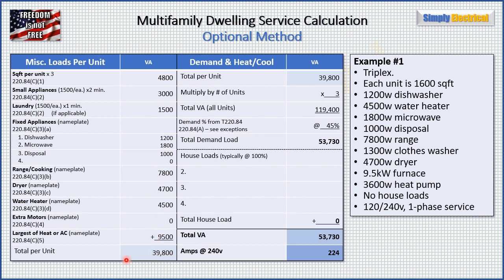Now we apply our demand factor from table 220.84. Three units gives us a demand factor of 45%. So 45% of 119,400 is 53,730 VA — that's our total demand load. We have no house loads, so 53,730 is our total VA. Divide by 240 volts single phase, and that gives us 224 amps. That is our service size.